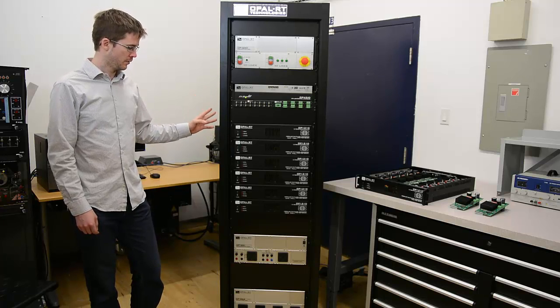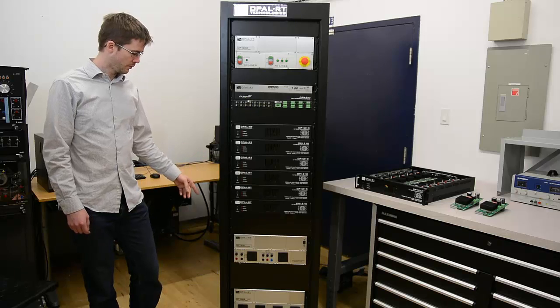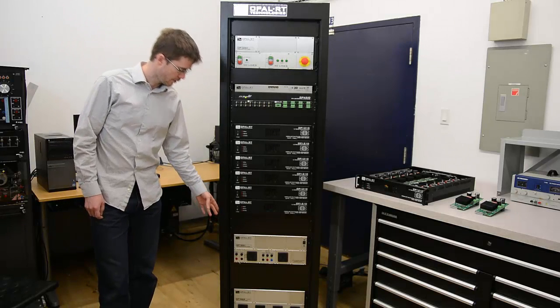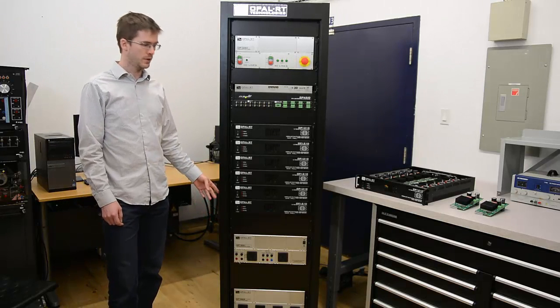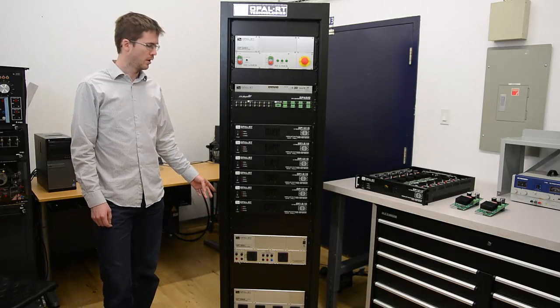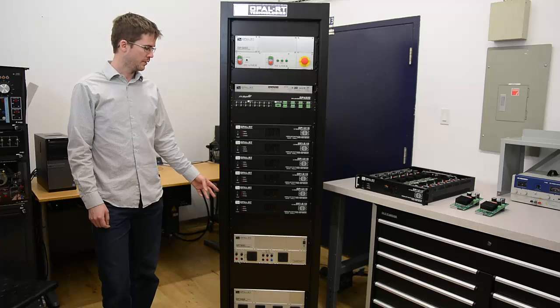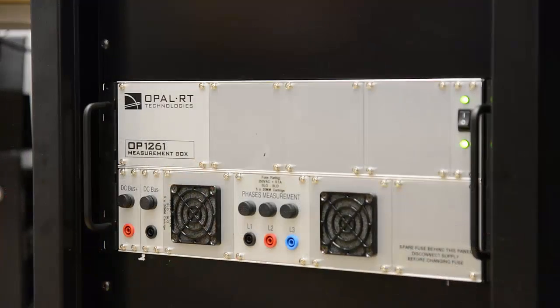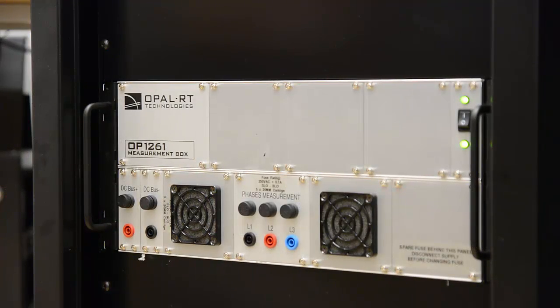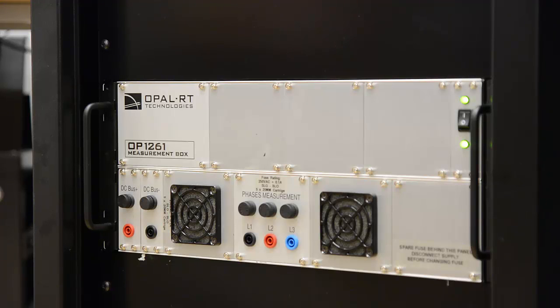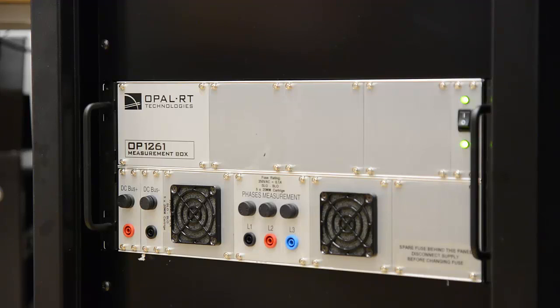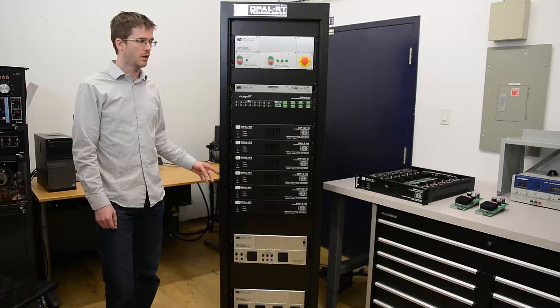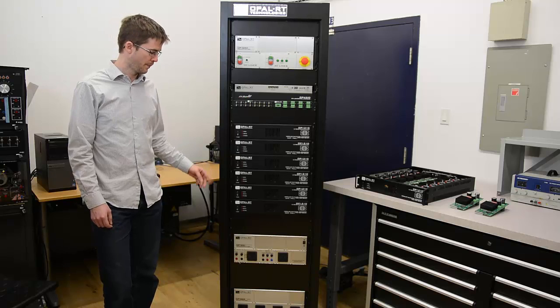Next is the measurement box, which is a grid connection unit that has measurement sensors to measure AC and DC grid voltage and currents. Plus it includes pre-charge resistors with bypass contactors to enable a realistic pre-charge sequence.